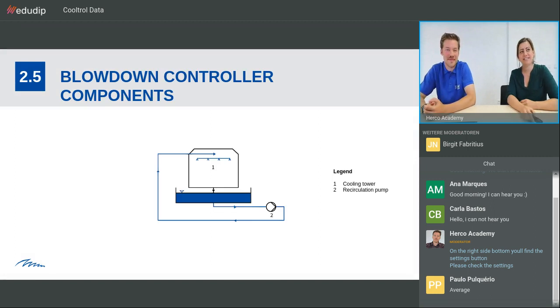So after this, we're going to go on with the components of a blowdown controller. So we're gonna start with the cooling tower itself. That's what you see here. The cooling tower, where water is sprayed over nozzles. You can see that on top, and water trickles down through the cooling tower. It gets collected in the cooling tower basin that is shown here. And then we have a recirculation pump, which is the number 2, which pumps the water back up to the top, where it is again passing the nozzles and going to trickle down.